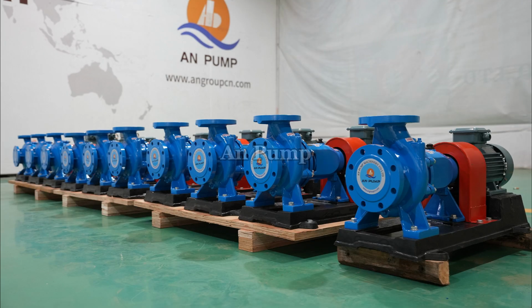So let's do a quick side-by-side comparison. End suction pumps are best for general industrial and HVAC service. They handle clean to mildly contaminated fluids, with medium head around 500 feet, and maintenance is easy with back pull-out design. Split case pumps excel at high flow water and fire suppression. They handle clean water, with medium-high head around 600 feet, and maintenance is excellent because of the split casing.